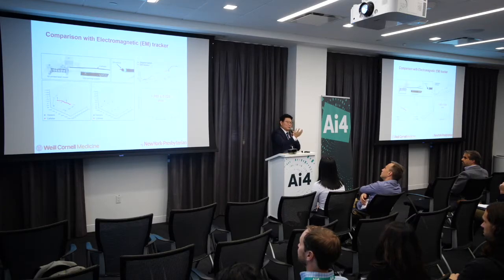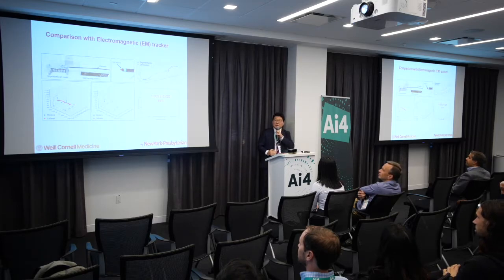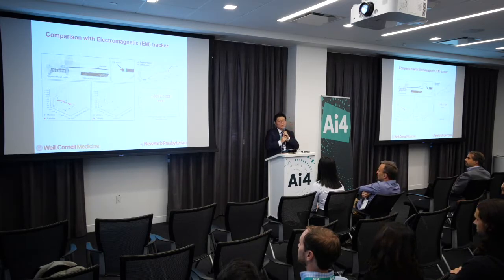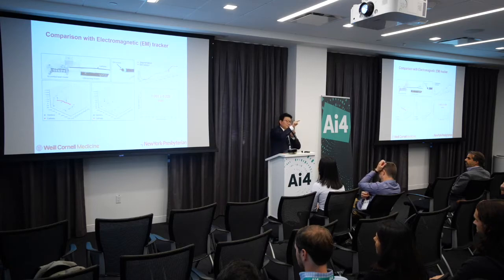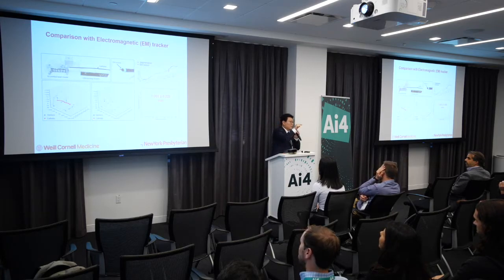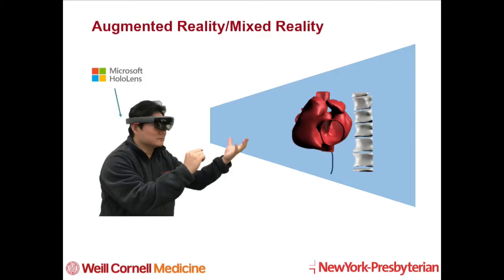One thing not yet mentioned is that the heart is contracting and moving. The CT scan is taken in a diastolic phase using ECG-gated scanning — stacks are acquired only when the heart is minimally moving. However, there is still cardiac motion, so we checked how much the catheter tip moves while the heart contracts — approximately four to five millimeters. For precise puncture localization this inaccuracy could be a problem, so motion correction is still under development.